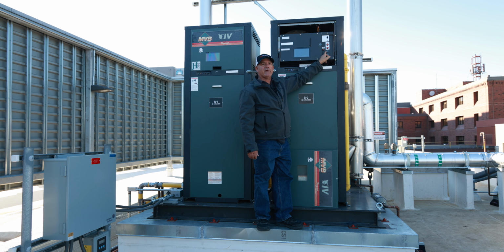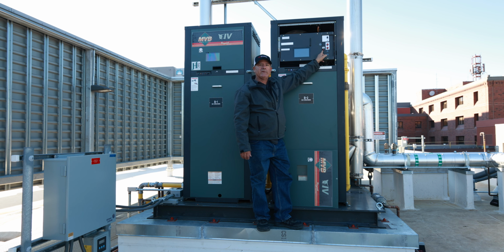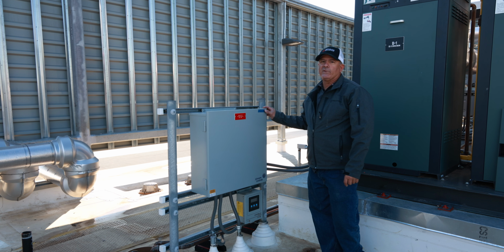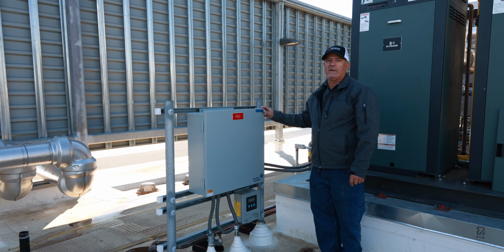Over here, let me step up here, guys. You do have a low water cutout, you have a test, and you have a reset. There's also another reset. This reset is to reset the boiler if it goes to alarm or has any kind of failure. This is your boiler temperature control panel. It's tied into the BMS.